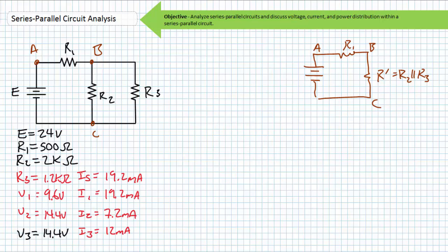Pertaining to the resolution of shorts and opens inside series parallel circuits, my only guidance is this: it depends. It depends upon the series parallel circuit, and it depends on where the short or where the open occurs within that particular circuit. This is to suggest that series parallel circuit analysis and troubleshooting isn't prefabricated drone work anymore, and you've got to really get down and dirty and think about it.